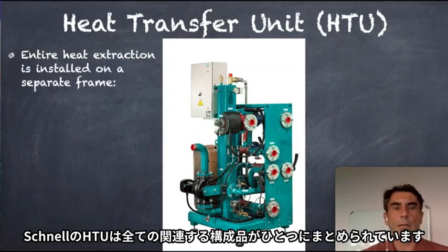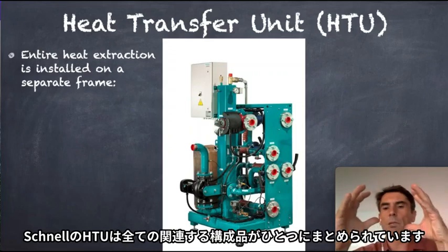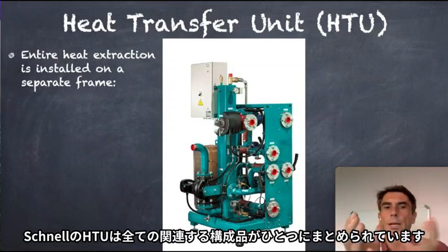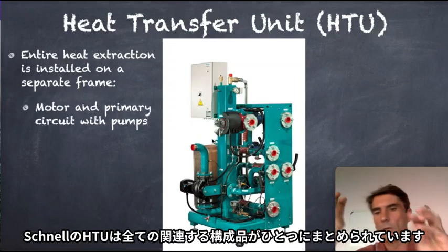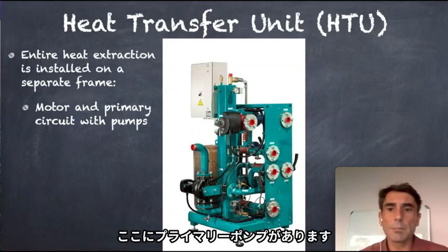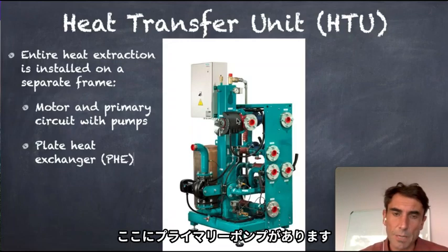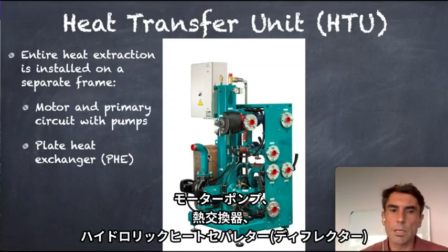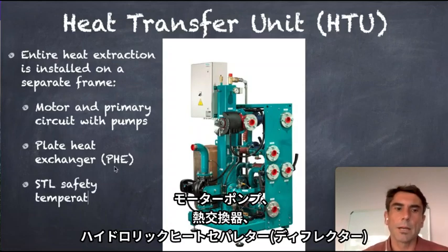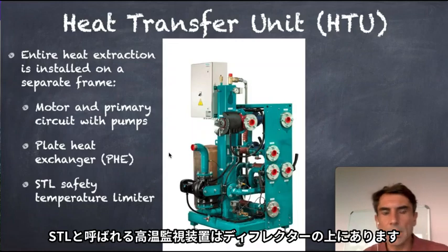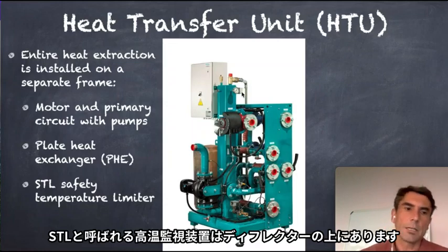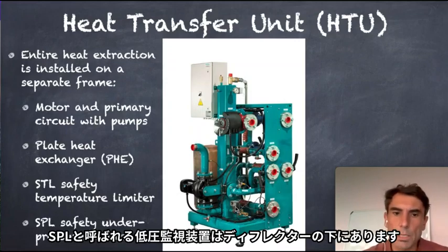Okay, so the design of the HTU is actually made that all components of the heat recovering or heat transfer unit are on one frame in one kind of unit. That's the idea of the design, that not all parts are different somewhere on the walls or separate. So on the whole system here on the HTU, we have the primary pump, we have the motor pump, we have the plate heat exchanger installed, we have the hydraulic separator here, up, right, down, and we have the safety temperature limiter. So this is that one up here. So the STL safety temperature limiter is a temperature switch. And then as well we have the under pressure switch, what's mounted under here.